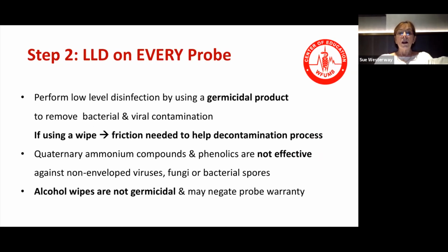Step 2, low-level disinfection on every probe. We perform this by using a germicidal product to remove the bacterial and viral contamination. If we're using a wipe, then friction is needed to help the decontamination process. It is no good just giving a simple pull up and wipe over the top. You actually have to rub the transducer to activate the ingredients in the wipe. Quaternary ammonia compounds and phenolics are not effective against non-enveloped viruses, fungi, or bacterial spores. And alcohol wipes are not germicidal and may negate the probe warranty.